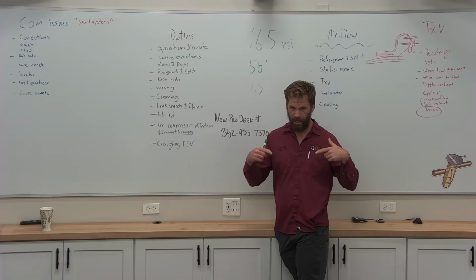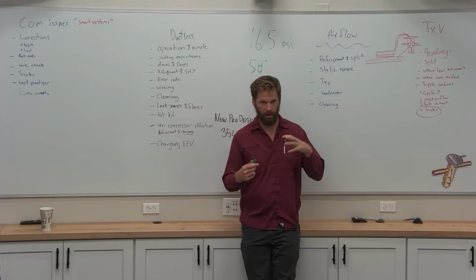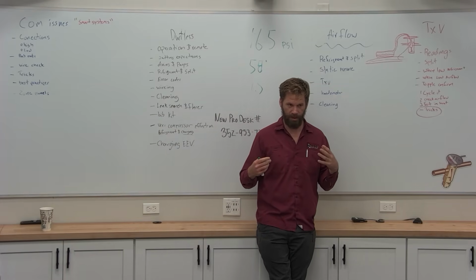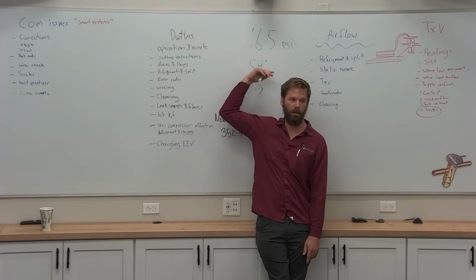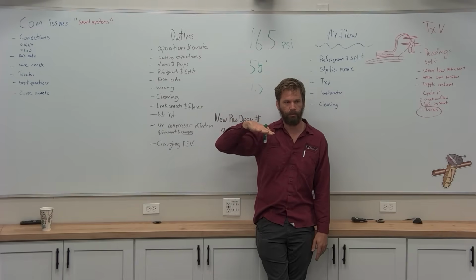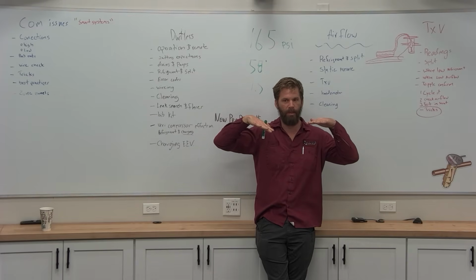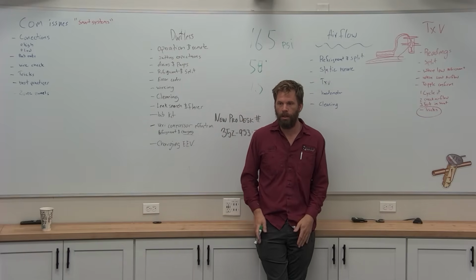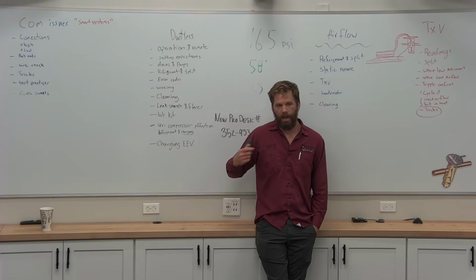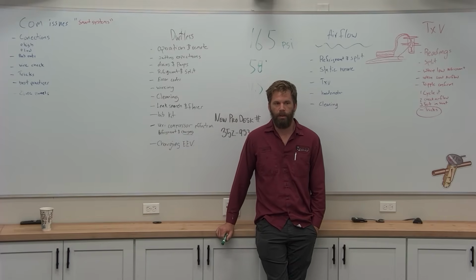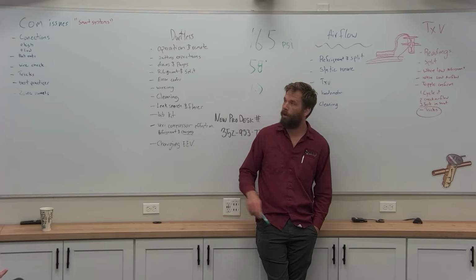So when it came on full speed, the coil would start to get cold enough to go into the freezing stage, and it would bring the compressor down to a lower speed. The suction pressure would come up, that way it doesn't freeze, and then the system would just shut off and wait for a little while and come back on. So it was really hard to figure out what was going on. It turns out it just needed more airflow inside to keep the coil above freezing.